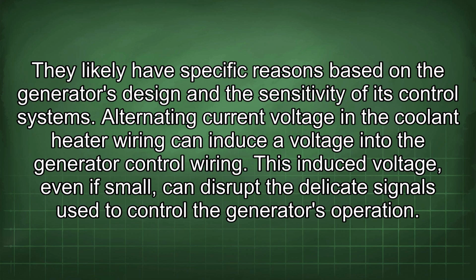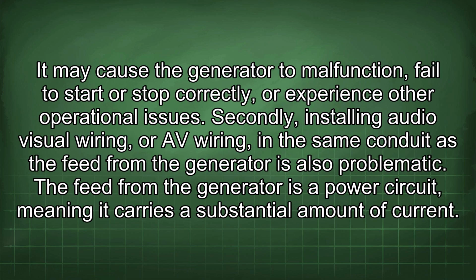Alternating current voltage in the coolant heater wiring can induce a voltage into the generator control wiring. This induced voltage, even if small, can disrupt the delicate signals used to control the generator's operation. It may cause the generator to malfunction, fail to start or stop correctly, or experience other operational issues.